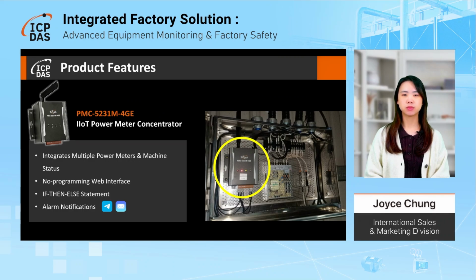In this case, the customer installed the PMC5231M4GE power meter concentrator to integrate multiple power meters and machine status information. Users can finish the setup without the need for programming. Another standout feature of the PMC power meter concentrator is its if-then-else statement capability, which allows it to activate related equipment during emergencies. Additionally, it can issue real-time alarm notifications through Telegram or email, ensuring swift responses of maintenance personnel in critical situations.